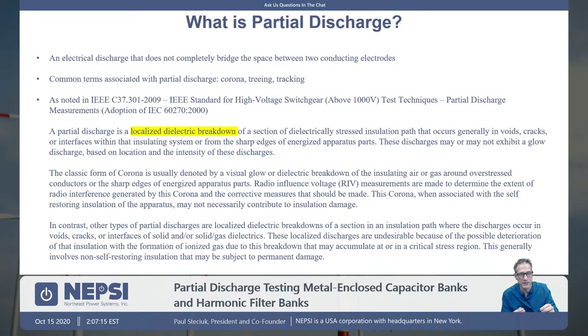When you see cable testing, the same thing. That's partial discharge you're hearing. You don't actually get the flashover. You won't get the lightning strike that you saw last week on the impulse test. Partial discharge is enough discharge to cause damage to the insulation, and it's quite repetitive, but it doesn't result in flashover. But it causes damage to the insulation. That's really the key here. If we were to continue to increase that voltage, the partial discharge would become so great that you would end up with a flashover. And that's what happens during withstand tests if you do not have the proper design.